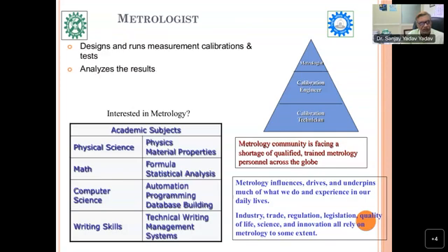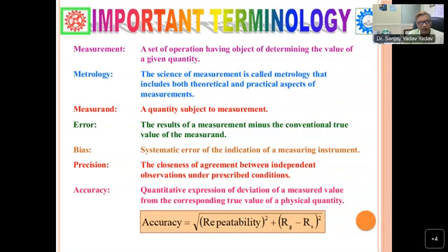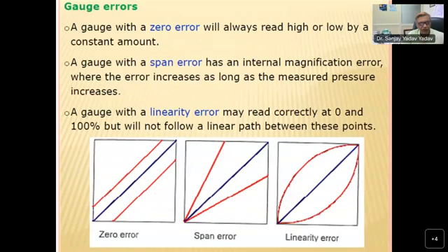So what does a metrologist do? They design and run measurements, calibration and tests, analyze the results, and determine the final accuracy of the device under test. This slide I have covered, but for the accuracy definition you have to use this equation. You need the repeatability, determined from the standard deviation, and then (gauge reading minus standard reading) squared. Normally people do (RG minus RS) squared divided by 100, but in the actual definition we should also use the repeatability of the measurement. Then there is zero error, which is constant throughout, span error, which increases with range, and linearity error.